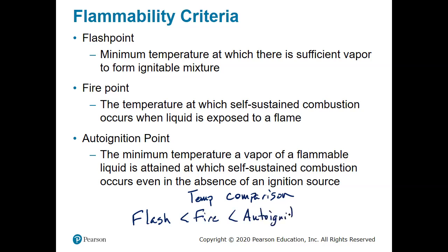And as you might expect, if we are to compare the three temperatures to each other, each one is going to be successively higher. The flash point of a liquid is going to be lower in temperature than its fire point. The fire point is going to be lower in temperature than its auto ignition point, if it has one.